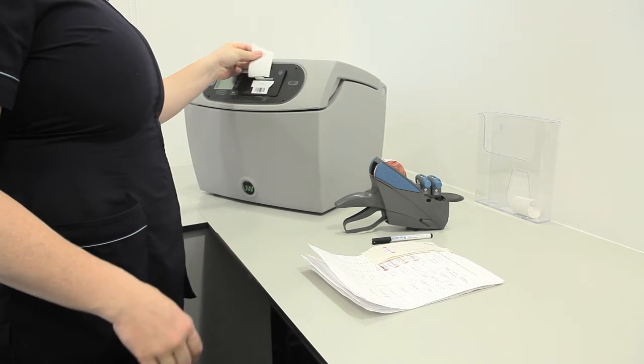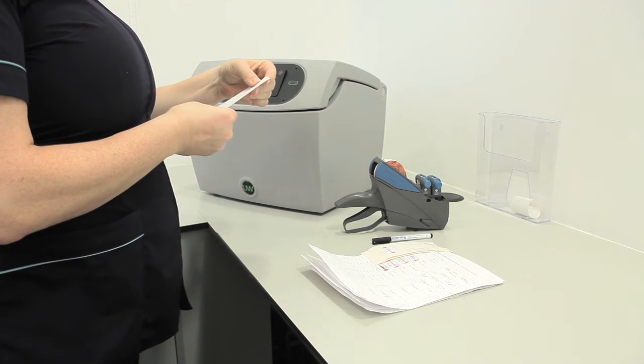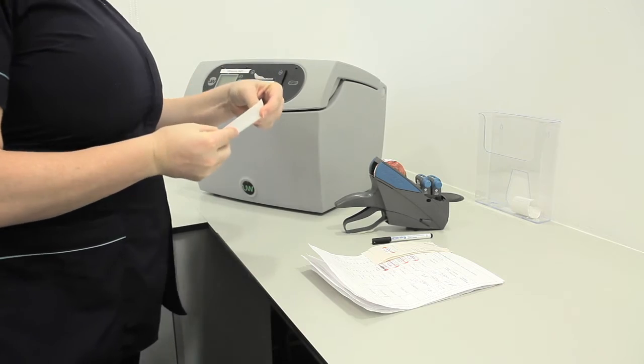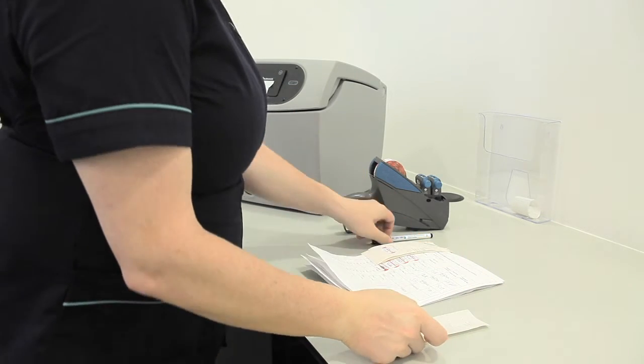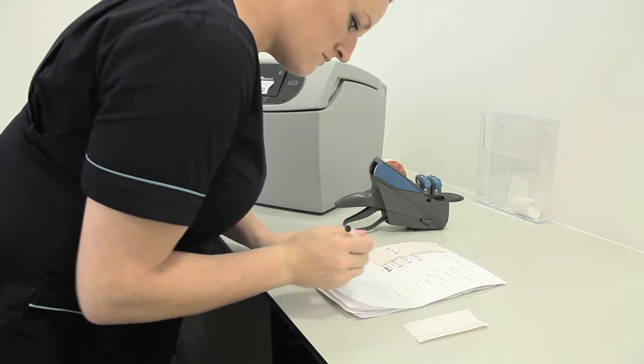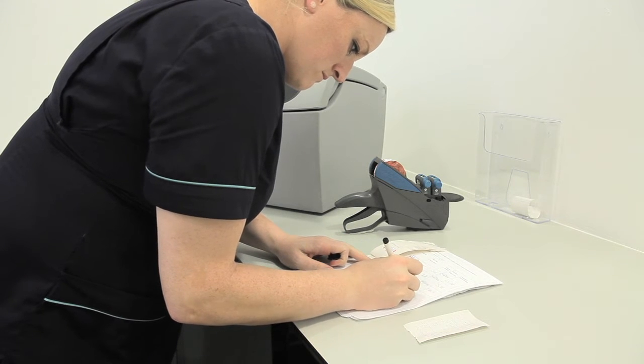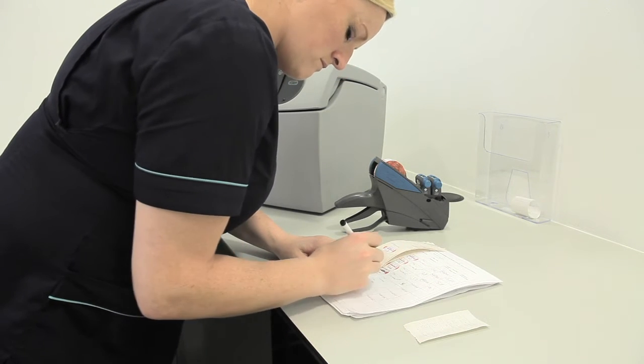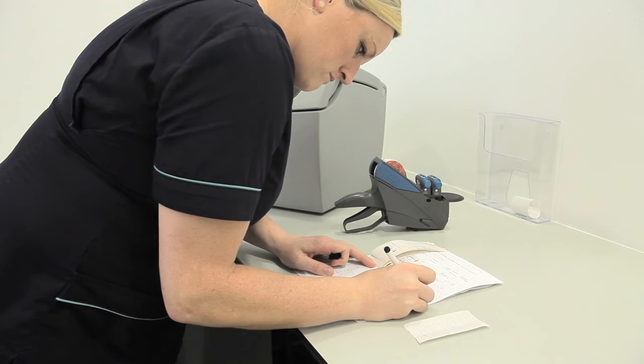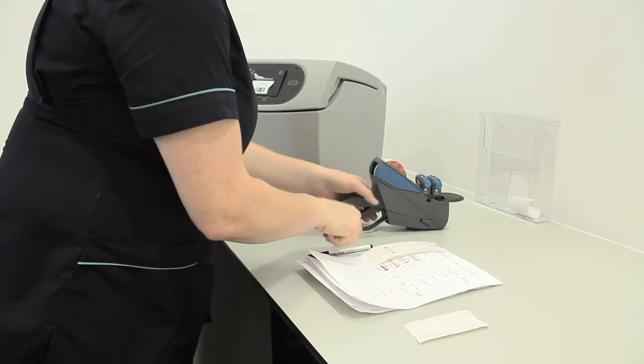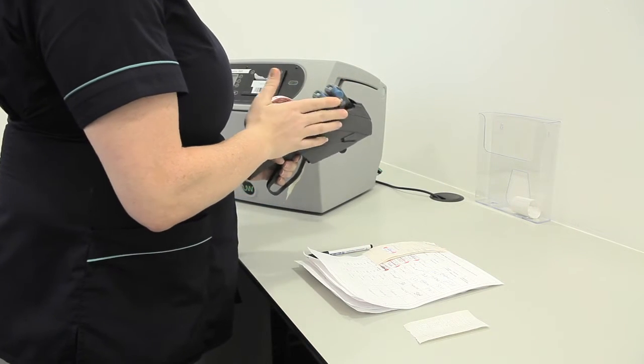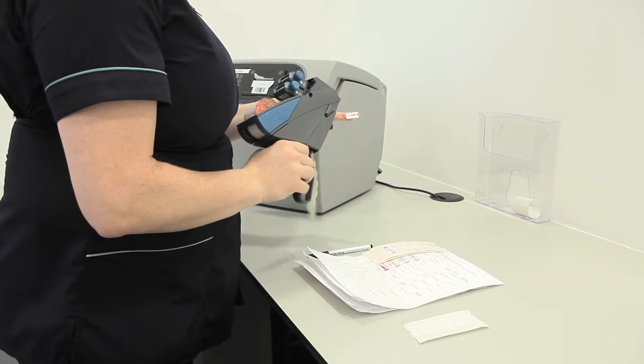As a minimum, a manual tracking system should be in place to record the progress of RIMD through each stage of the decontamination process and allow retrospective demonstration that a particular cassette or single item RIMD has been correctly decontaminated. By having a tracking system in place, the organisation can prove the sterility of the RIMD which are used for patient treatments.